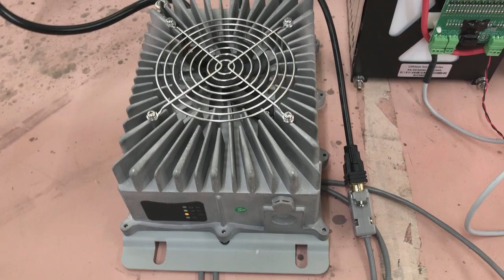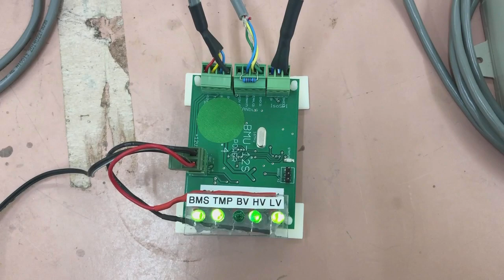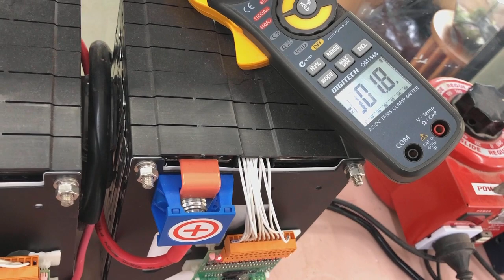At the moment we also have a charger here, the A series charger. It's a 100-volt charger, but it's controlled by the CANbus, which comes back from our BMU 12S. The BMU 12S has a CANbus output that directly controls the charger, so the charge curve lives in the BMU, not the charger. The charger is basically just a dumb power supply. Right now it's in balancing mode, only supplying about 1.8 amps into the batteries because they're nearly at the top of their charge.